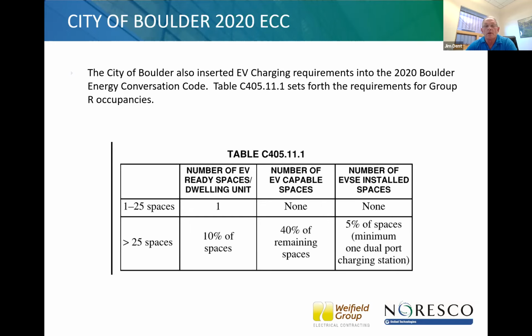The City of Boulder also inserted EV charging requirements into the Boulder Energy Conservation Code, and Table C405.11.1 sets forth the requirements for Group R. So for greater than 25 spaces, the number of EV ready spaces per dwelling unit is 10% of the spaces. The number of EV capable is 40% of the remaining spaces. The number of EVSE installed spaces is 5%.